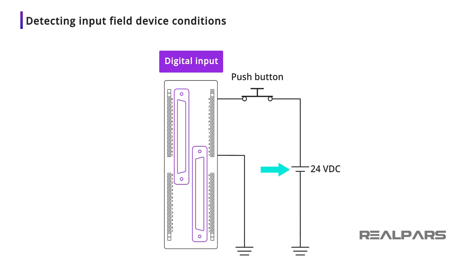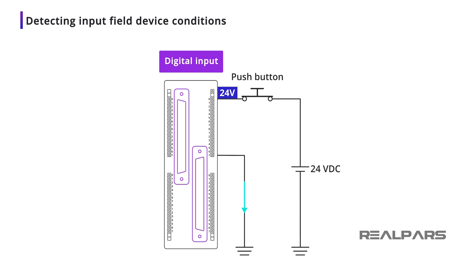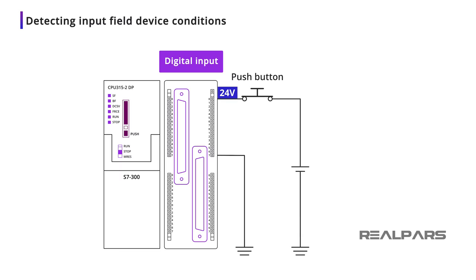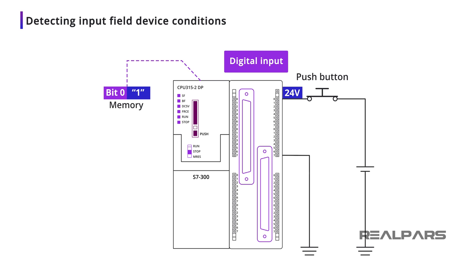If the switch is open, there is 0 volts at the module input terminal. If the switch is closed, there is a positive 24 volts at the module input terminal. The input module will detect either a no-voltage or voltage condition at the input. These voltage conditions represent the open or closed conditions of the switch, and are represented by 1s and 0s in the PLC memory.